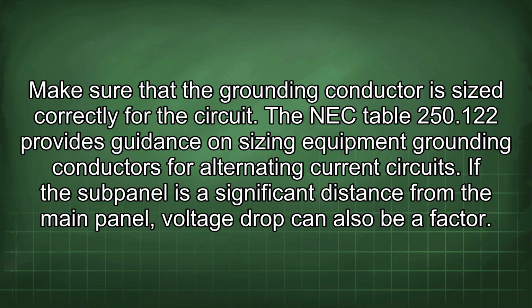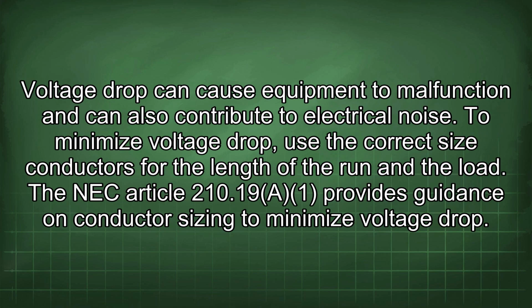If the subpanel is a significant distance from the main panel, voltage drop can also be a factor. Voltage drop can cause equipment to malfunction and can also contribute to electrical noise. To minimize voltage drop, use the correct size conductors for the length of the run and the load. The NEC Article 210.19 provides guidance on conductor sizing to minimize voltage drop.